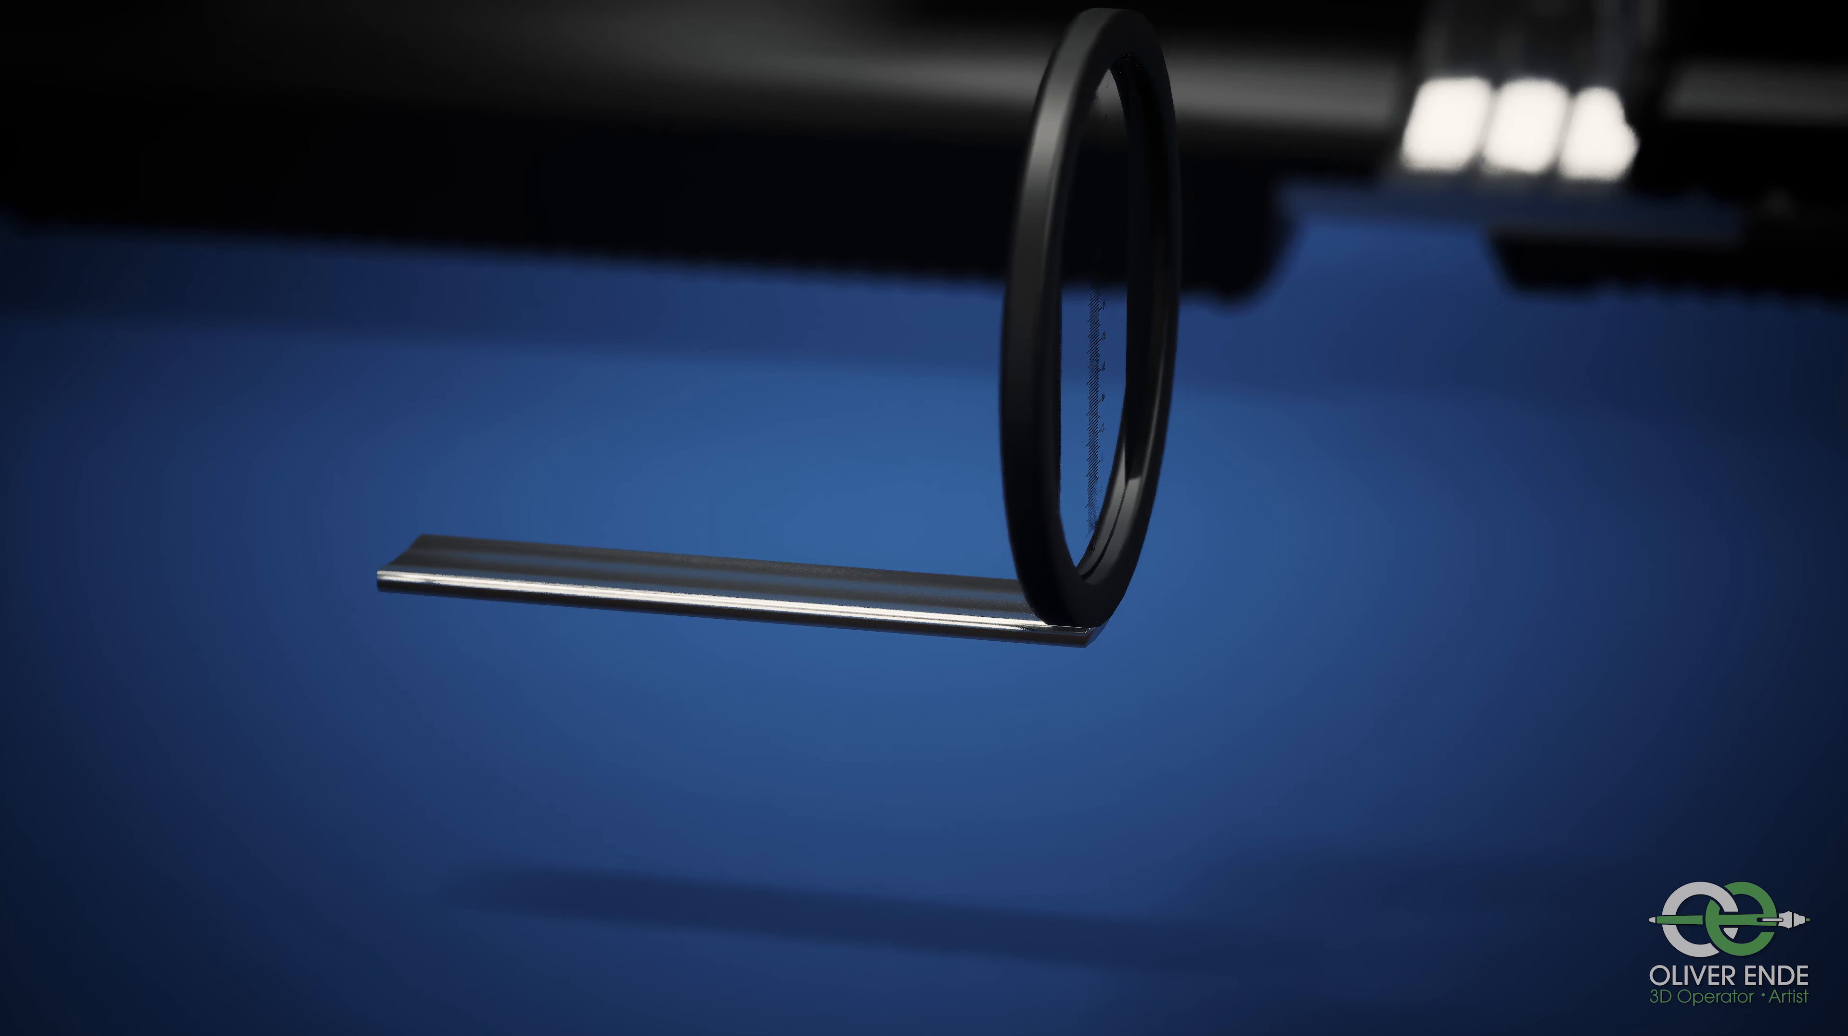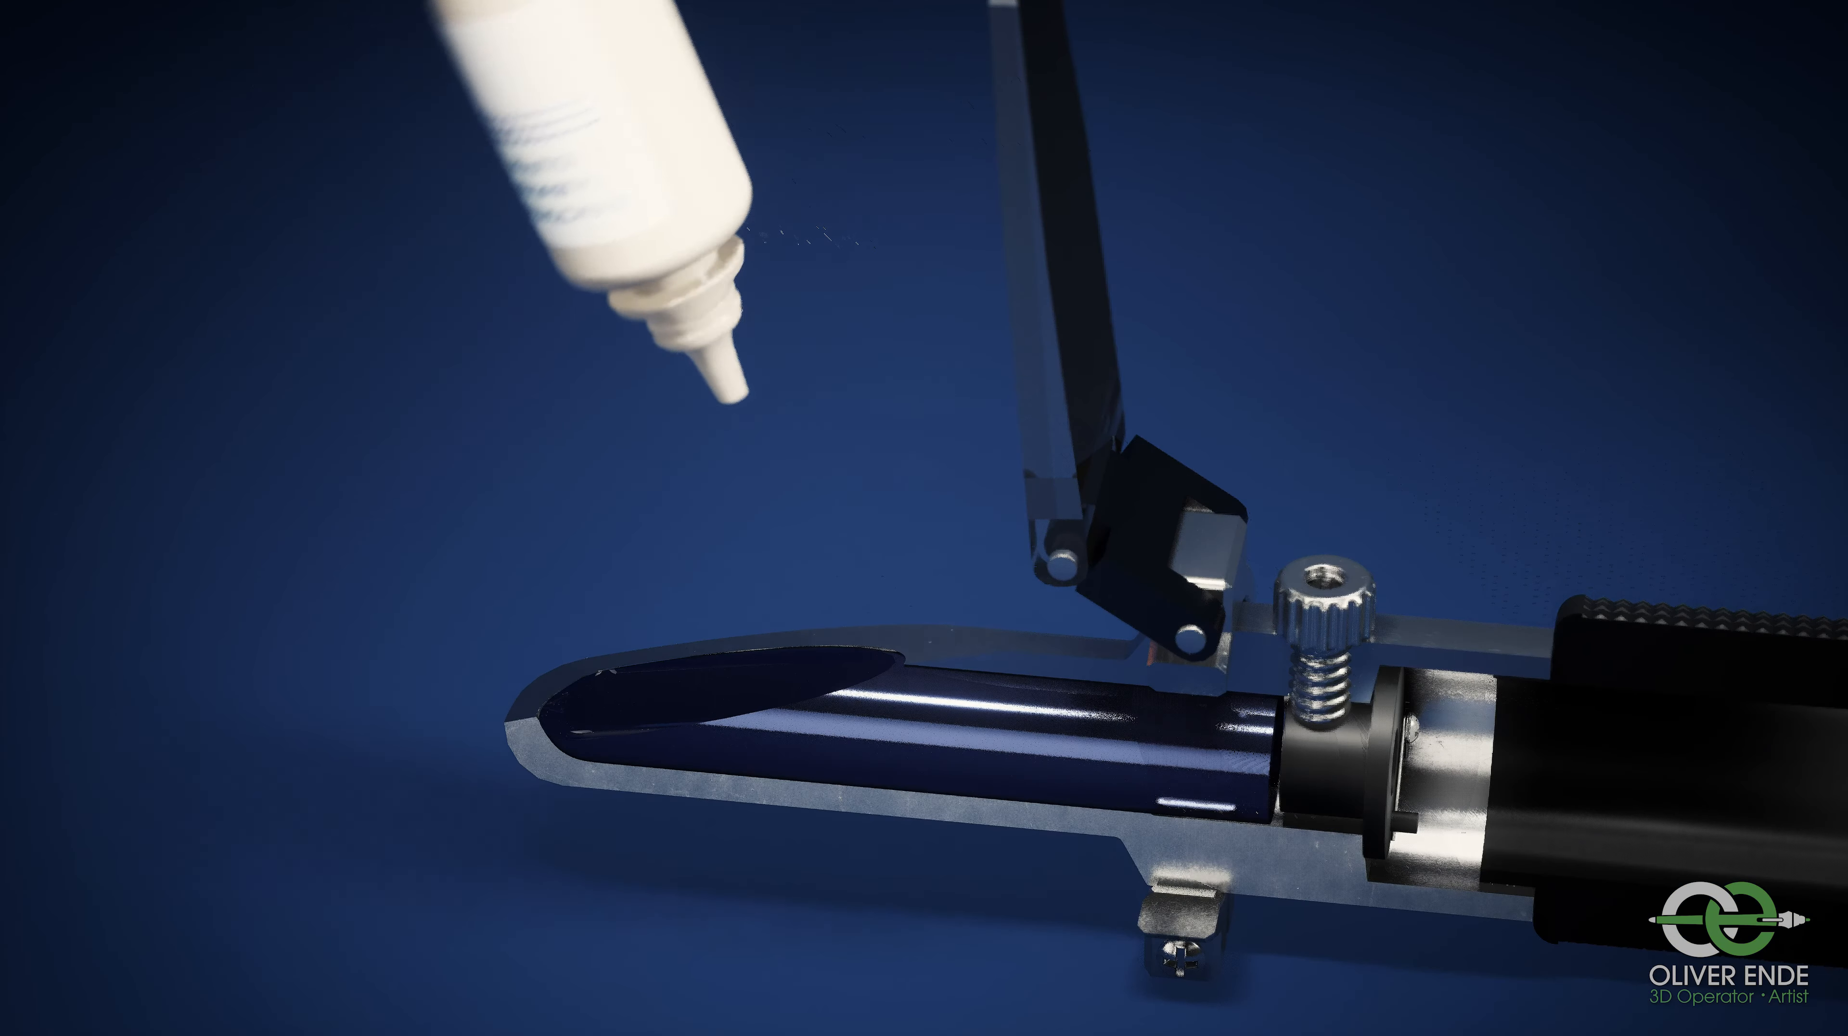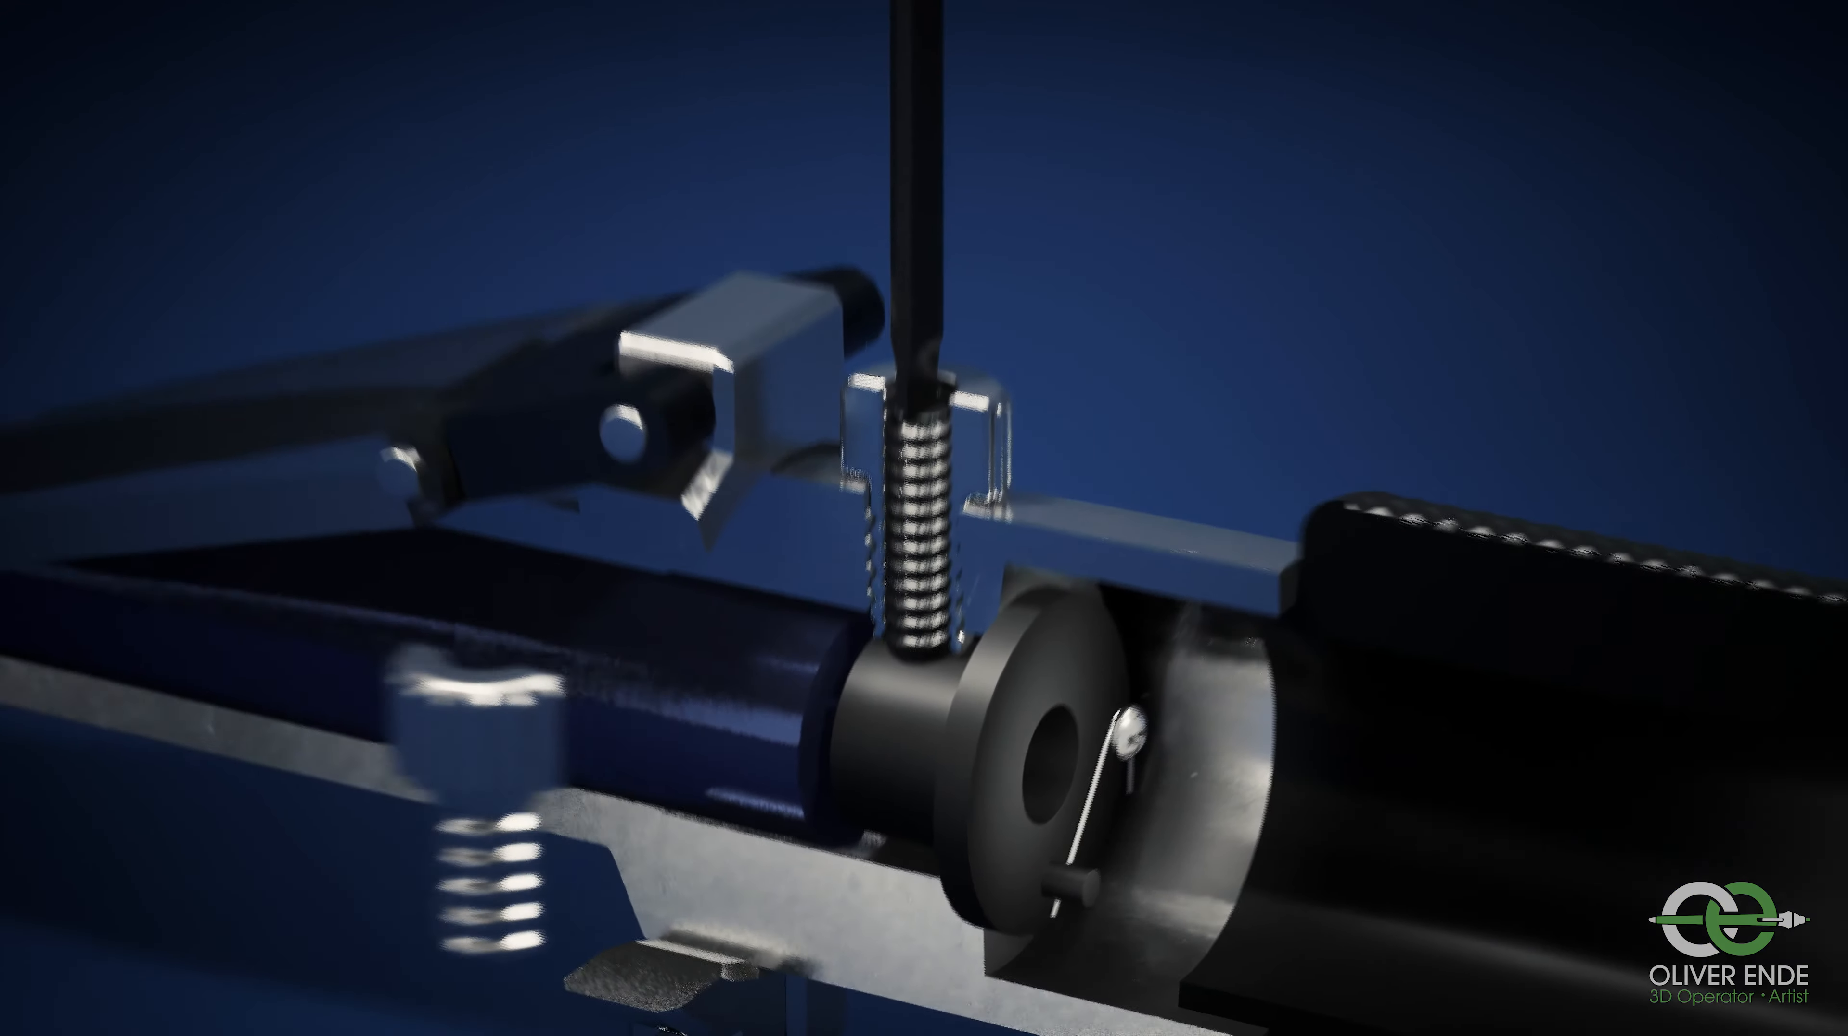A refractometer is calibrated by dropping a so-called reference or calibration solution onto the prism. If the measurement result does not correspond exactly to the reference value of the solution, you can adjust the calibration screw with the screwdriver until the value matches as closely as possible.